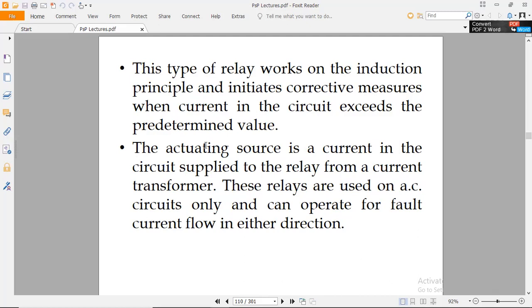So the predetermined value needs to be compared with the upcoming value, and that upcoming value is produced by the fault, under abnormal conditions like overvoltage and undervoltage. During the fault conditions, the predetermined value would be matched with the user-defined value. The difference would then be provided as an action to the circuit breaker for the tripping operation.